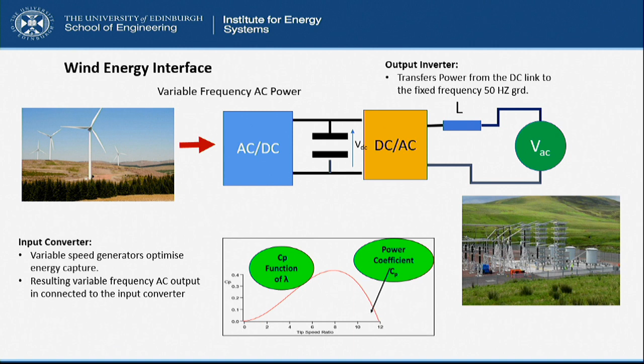At a minimum, it's got to be synchronized to 50 Hertz. It's got to change its phase angle to be able to control the power. And it's got to react to a whole load of contingencies on this grid, such as faults, and do that in a way that doesn't damage the power electronics and acts benignly, helpfully towards the grid.